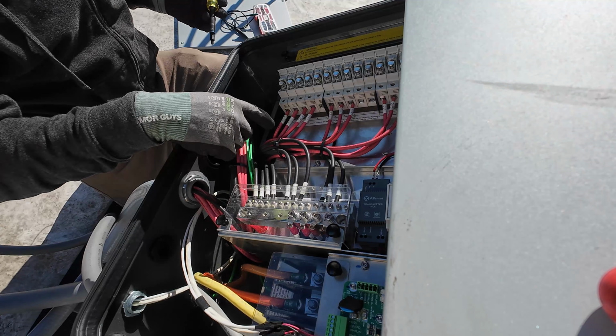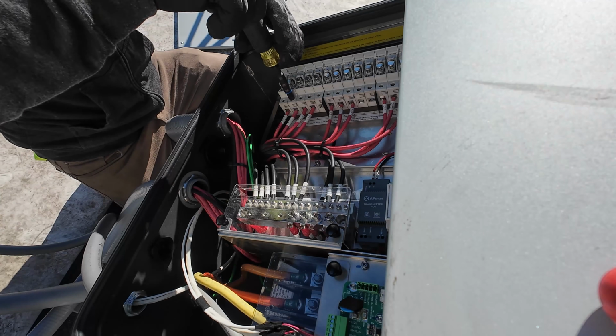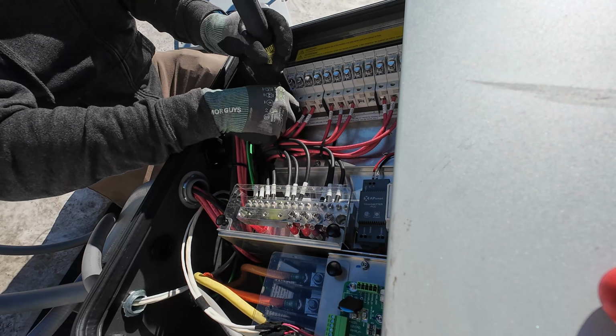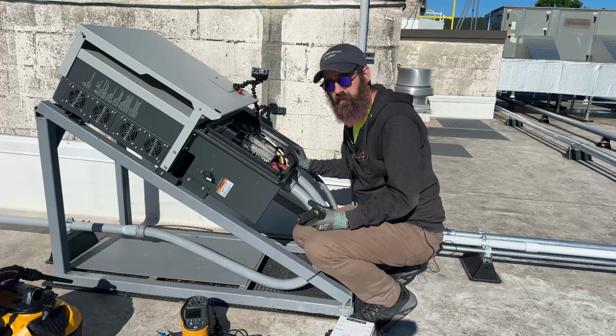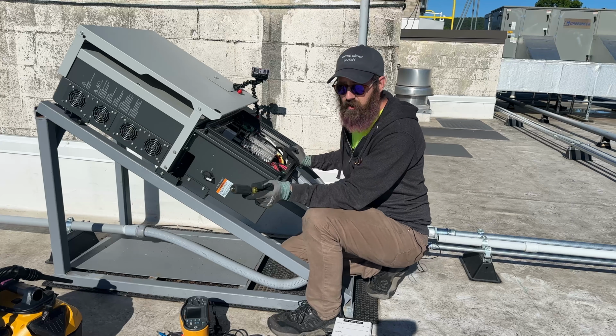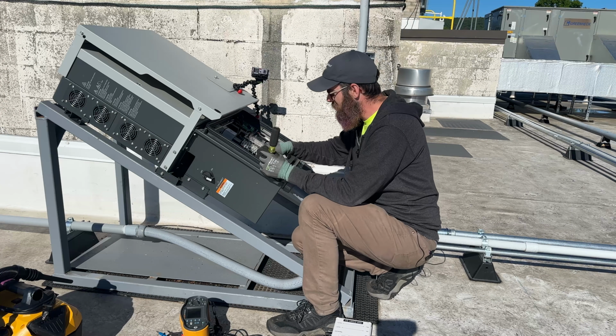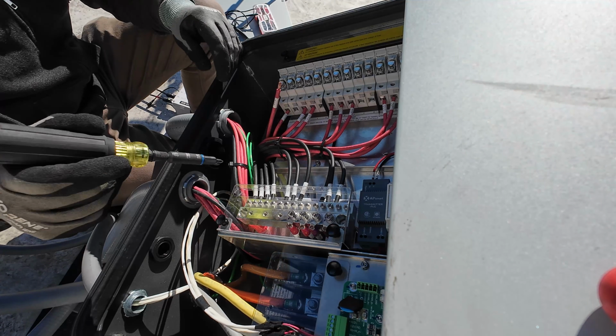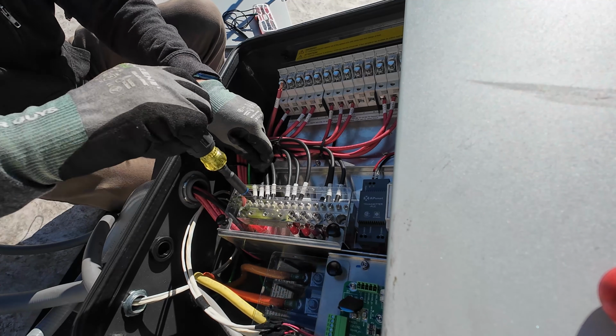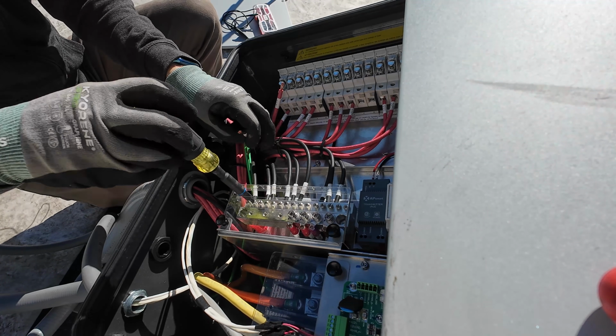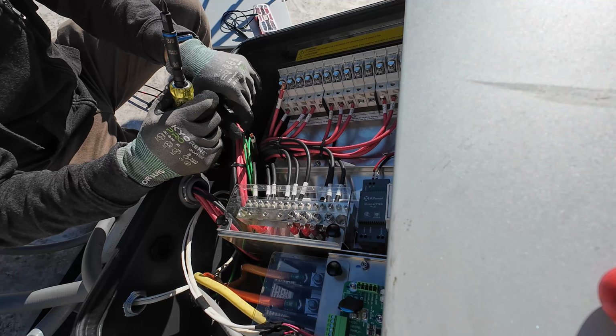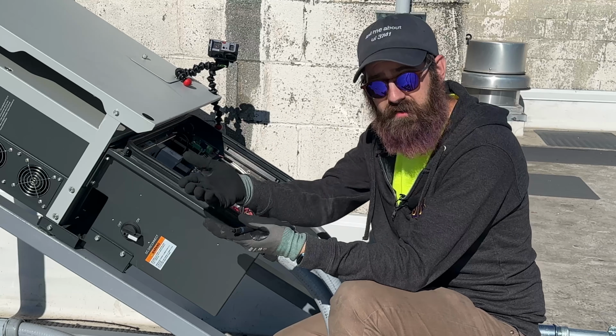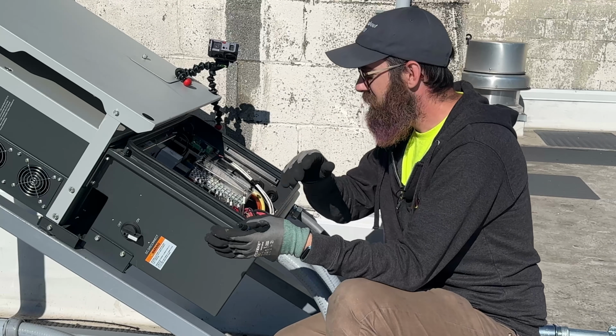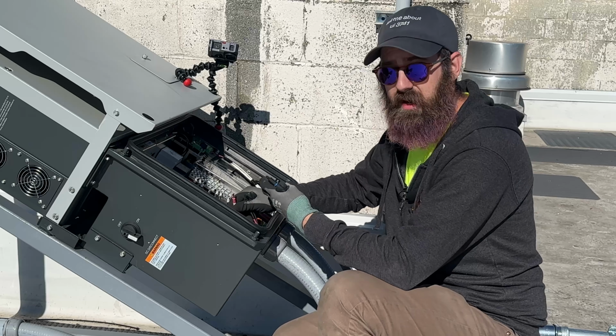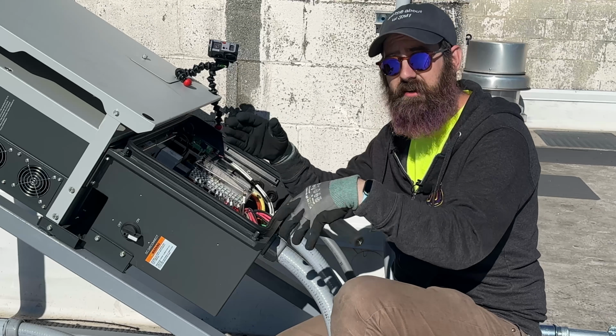We're gonna actually test F12 here, because F11 is on another array. And the fun thing about a string being on another array that's already producing is that you can get crosstalk between strings. So if you have a string running alongside several other strings that have the power-on signal on them, these strings can pick that up too, just inductively.